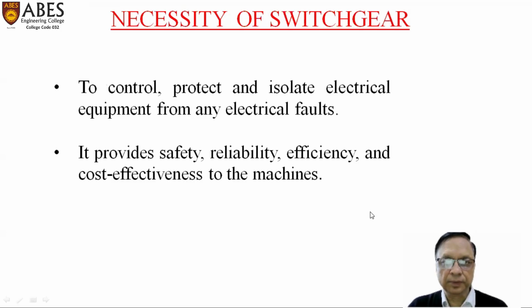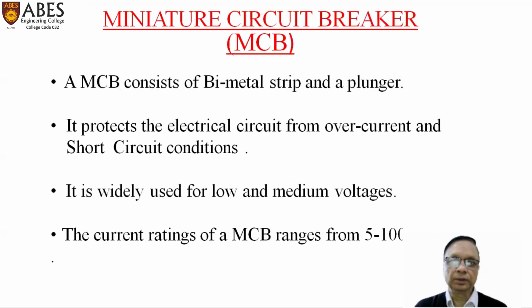That is, to control, protect and isolate electrical equipment from any electrical faults, and to provide safety, reliability, efficiency, and cost effectiveness to the machine. Now, what is an MCB? MCB is a miniature circuit breaker. Its full form is miniature circuit breaker. We have seen it in our households. In our houses, it is installed at the main supply. It consists of a bimetal strip and a plunger.